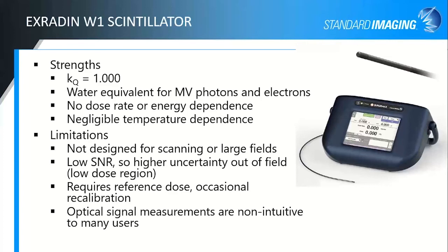Limitations of the W1: it's not designed really for scanning or for large fields. It is a small field detector. It does need to be used with a 2-channel electrometer like our Supermax. We have a scintillation routine built into here so that it will automatically do that Cherenkov calculation and correct your measurements for you. But you do need to have that 2-channel electrometer to work with it.